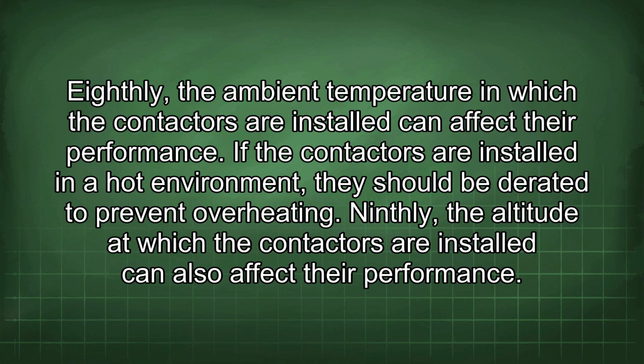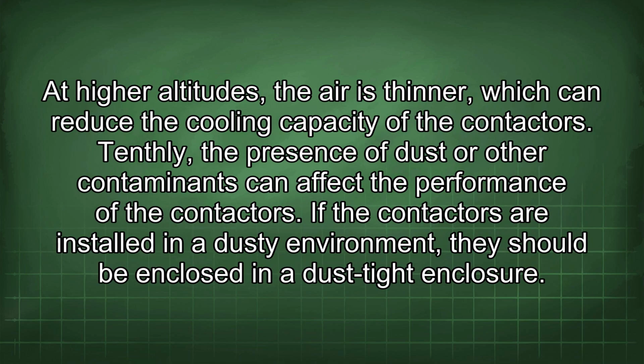Ninthly, the altitude at which the contactors are installed can also affect their performance. At higher altitudes, the air is thinner, which can reduce the cooling capacity of the contactors. Tenthly, the presence of dust or other contaminants could affect the performance of the contactors. If the contactors are installed in a dusty environment, they should be enclosed in a dust-tight enclosure.